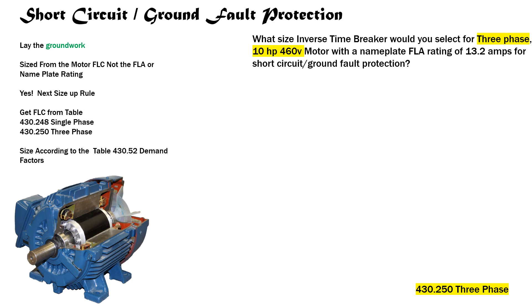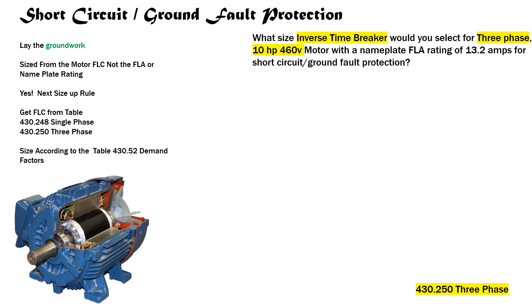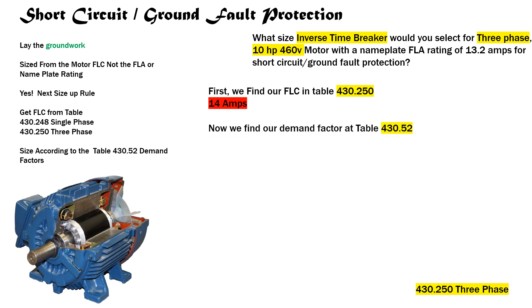The first thing to point out is that it's three-phase, 10 horsepower, 460 volt, and second, that it's an inverse time breaker. We'll find our FLC in table 430.250 — on the left-hand side we go down with our horsepower, then across the top to find our voltage, and we select our FLC. In this case it's 14 amps.